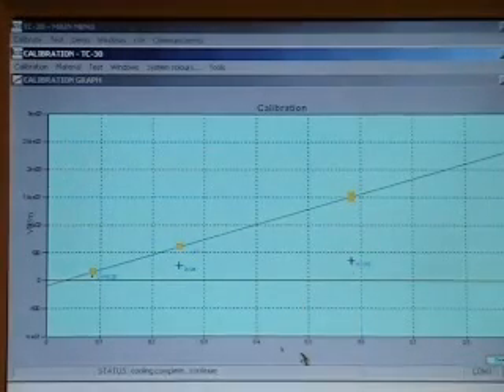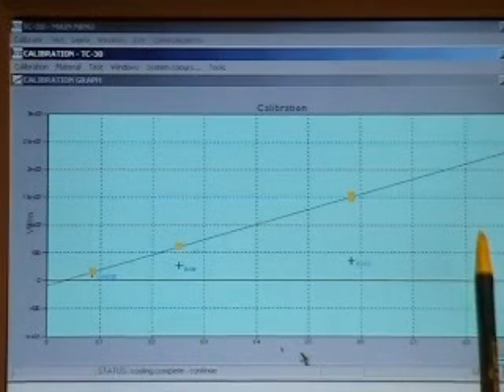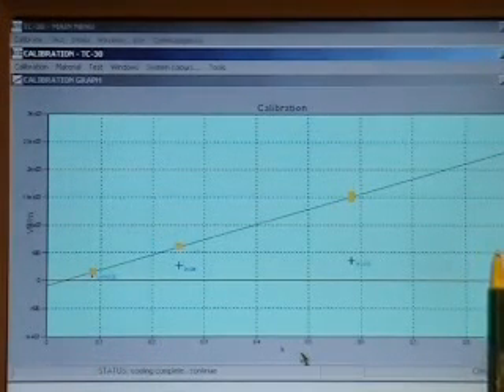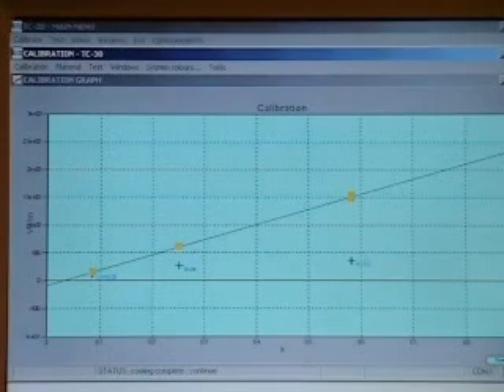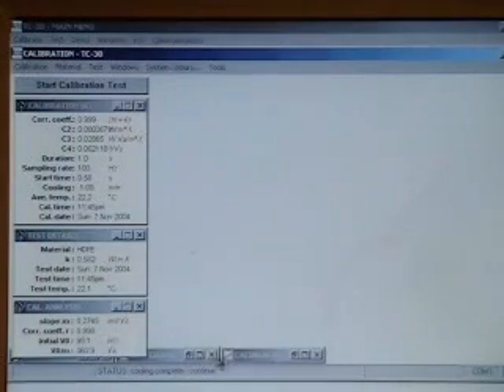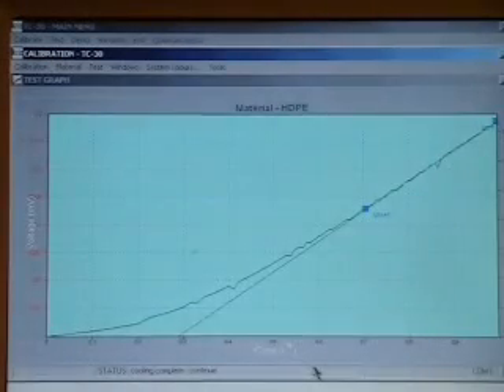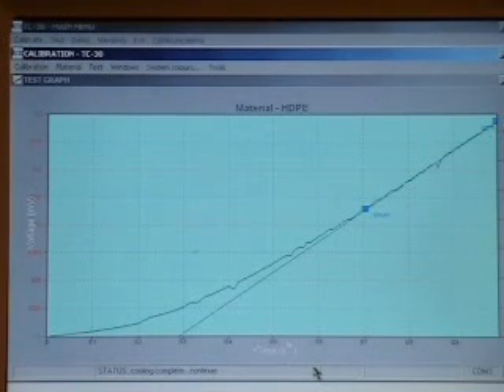Now that we've completed the calibration table, let's take a look at the calibration graph. This plots the instrument response, or the slopes of each test on each standard against each standard's thermal conductivity value. Let's take a look at the slope for HDPE. As you can see, there's a 0.5 second start time. This ensures we're beyond any effects of contact resistance between the sensor and the sample, ensuring we're in the linear portion of the temperature rise. Again, the slope comes from the start point to the end point of this line.